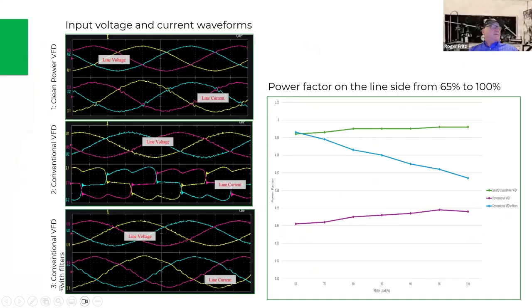This is a conventional drive with line reactors, and they mitigate it. This is just a straight conventional VFD, and you can look at the choppiness in the current waveforms. And then there's also, we'll get into it a little bit further, the clean wave output type. So you can see that the actual power factor on the line side stays continuously above almost 99% on the Smart D pure sine wave VFD. Compared to the conventional, it drops off dramatically, and the ones with filters are down here, but you can see that it's still about 94% power factor.